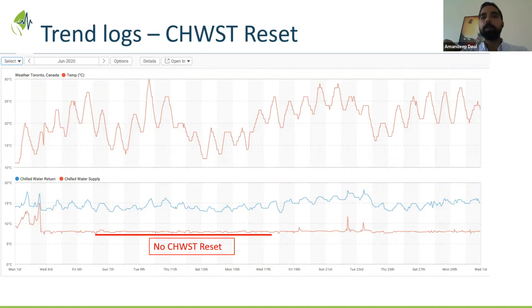So there's currently no automatic reset, which is what a high performing chiller plant looks like. Eventually you want to move into that transition, where you have automatic resets on the chilled water supply temperature. It could be temperature, or it could be your key on the load as well. So whatever system, whatever the programming works for you, but at least there has to be some sort of an automatic reset so that you can maximize the energy efficiency of your plant.